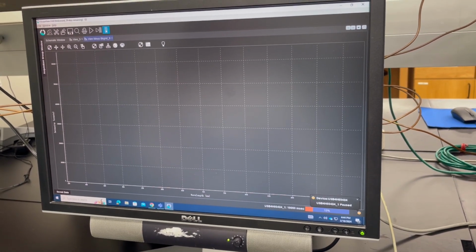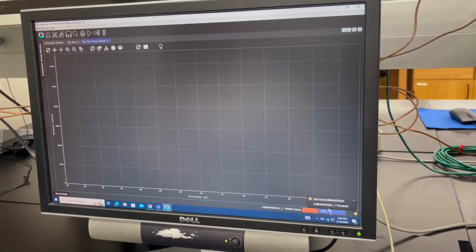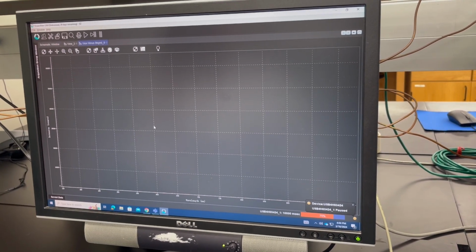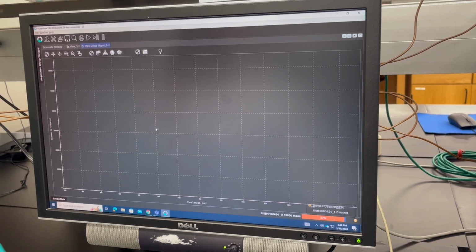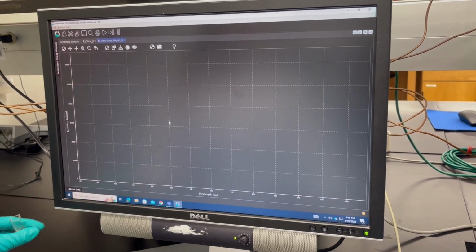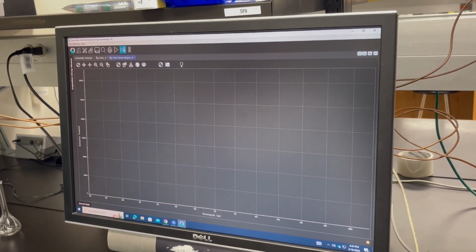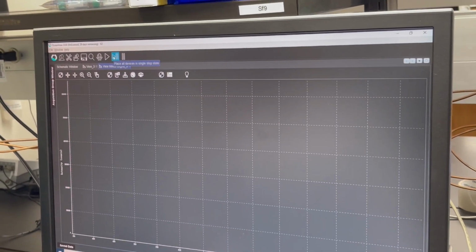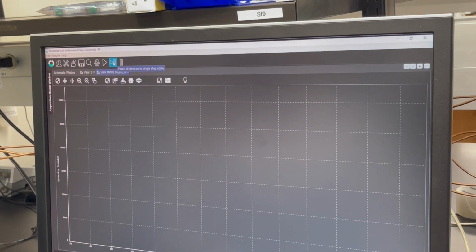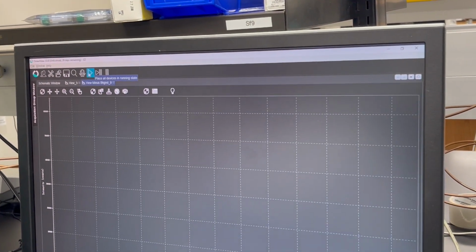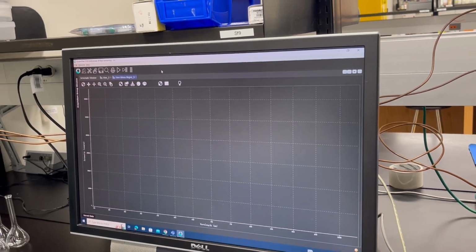And then you're gonna wanna pause because this device is just gonna keep running over and over again unless you pause it. And then for all of the samples that you run from here on out, I recommend you click the play pause button. This will do one run and then pause the instrument. If you did play, that will just continually do runs over and over again like it was doing, and you'll have to click pause after each one.